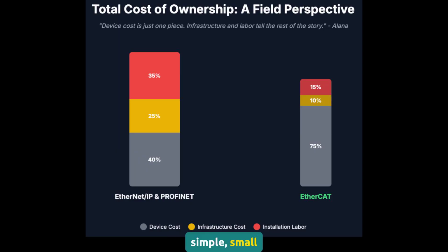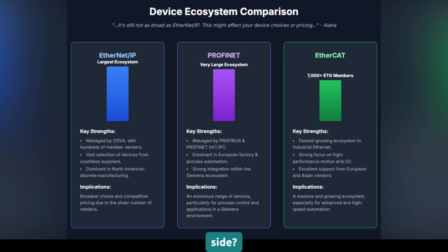So how should you think about the economics? Well, for simple, small systems, any protocol will work cost-wise. But as your device count grows or you need high-performance synchronization, EtherCAT's infrastructure savings become the deciding factor. You're comparing EtherCAT's device costs against PROFINET IRT's expensive specialized switches. EtherCAT wins that comparison. So what is the flip side? Ethernet IP has the broadest device ecosystem, which can mean more competitive pricing and more vendor options. Sometimes having 20 suppliers competing for your I/O business drives better deals than a smaller ecosystem.